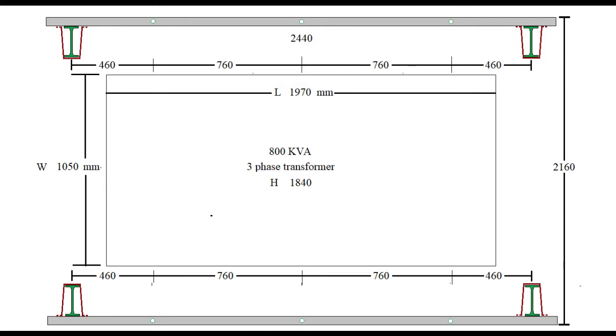This calculates to 2440 mm of distance between centers of poles. These two poles are such poles. Using them, equipment like air brake switch are fitted using channels. These channels may come along with the equipment, or the erector has to fabricate them. The other pair of poles shall also be 2440 mm away from each other.